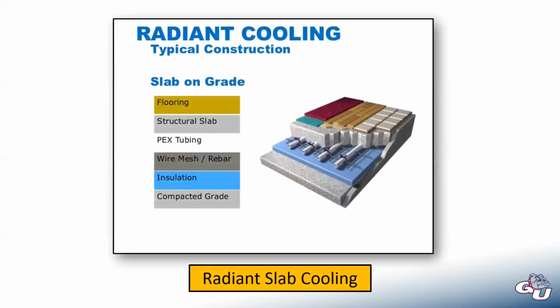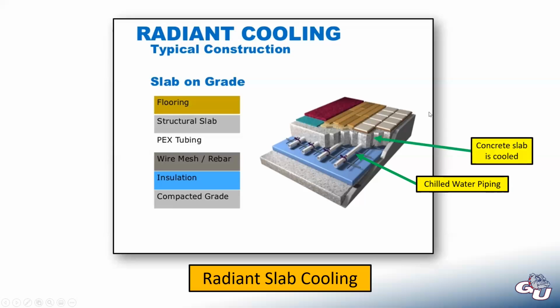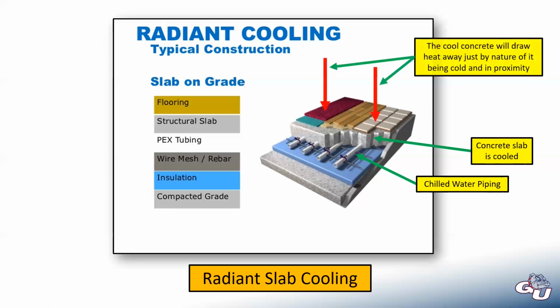To close this out, this has all been about radiant heat so far, but there are also radiant cooling systems. These are much less common. A radiant cooling system basically runs chilled water piping through your slab — about 55-degree water through this concrete slab, which cools the slab down. Then, because that concrete is cool, it draws heat out of the space. So as occupants walk over that concrete slab, they feel that cooling effect just from being close to the cool concrete.